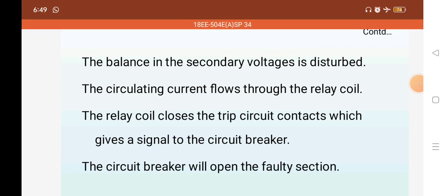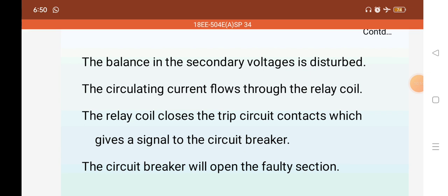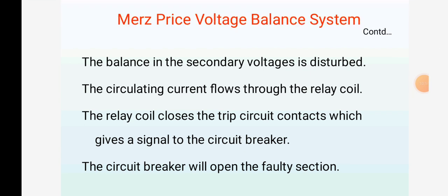The balance in the secondary voltage is disturbed. The circulating current flows through the relay coil. The relay coil closes the trip circuit contacts which gives a signal to the circuit breaker. The circuit breaker will open the faulty section.